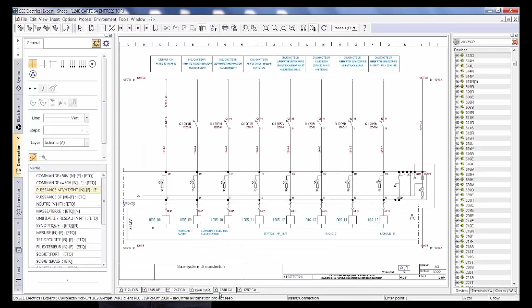This is an important trend. We know that there is much more to come and much to do in future to support mechatronics. First, See Electrical optimizing the communication between electrical design and the world of PLCs. Incorporating PLC in your electrical project normally represents numerous working hours in terms of creation, modification, and verification. The See Electrical and PLC configurator and programming tools data exchange solution will generate and update your I/O schematics automatically and reinject data derived from electrical diagram into the PLC software. See Electrical can connect to Siemens TIA Portal, Schneider Electric EcoStruxure Automation Expert, Rockwell Allen Bradley Logix, and more via a generic XLS format.